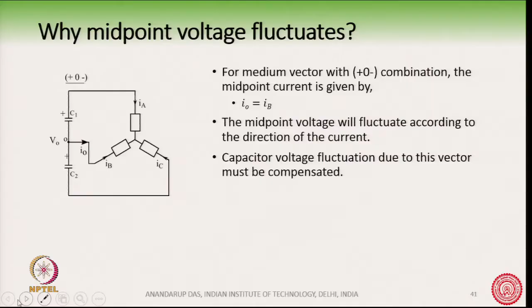Now, you see there is no multiplicity on the medium vector. So, if this medium vector is used, it will cause some fluctuation in the midpoint voltage or the capacitor voltage. It must be compensated, but there is no multiplicity on this vector unlike the small vector. This medium vector must be taken care of, because it will cause the voltage to fluctuate, but in sector 1 there is no one to compensate that. There is no switching state which can compensate the effect of the medium vector. So, it must be done through some other technique which we will see.